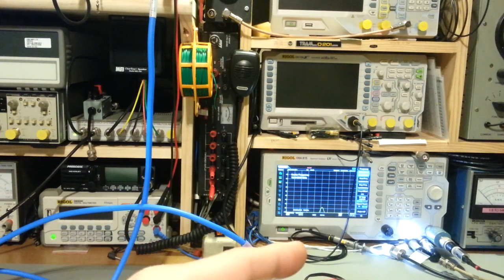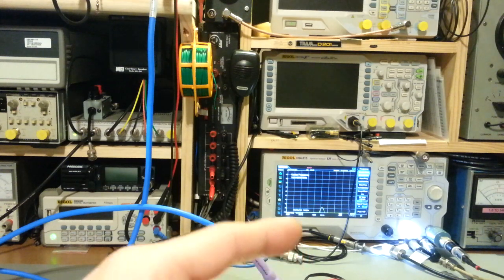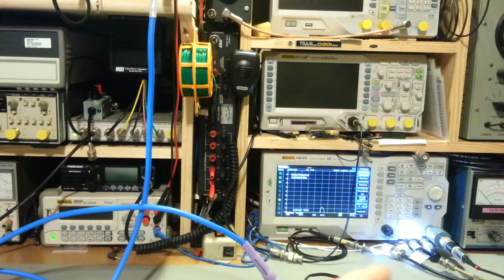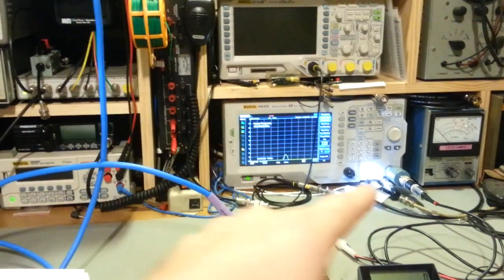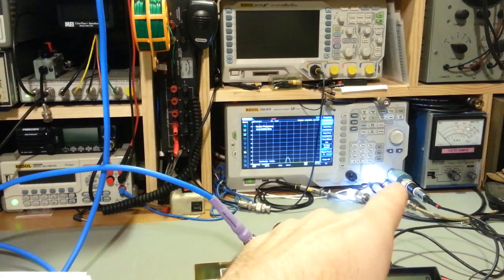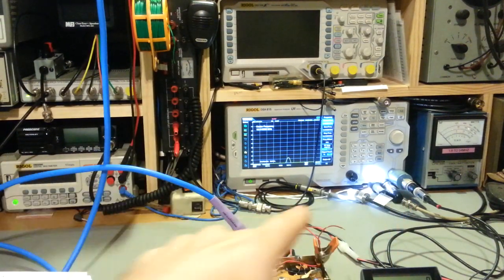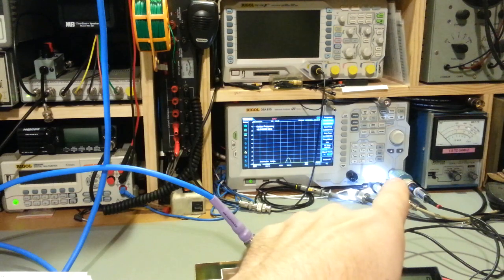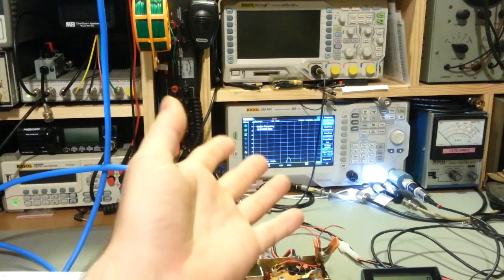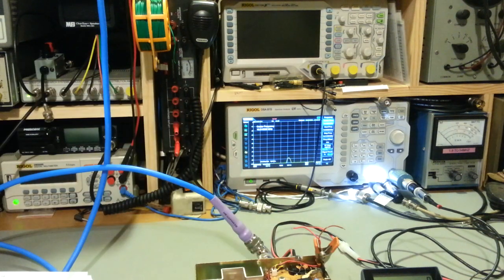They'll have a DC rating, usually printed on the front of your spectrum analyzer. It'll tell you what the maximum DC voltage is, but I always prefer to be better safe than sorry, and I put in what they call a DC block. I have a Narda brand right there, that blue thing. It's permanently attached; I just leave it there all the time. It's a DC block, and that prevents DC voltages from getting into my spectrum analyzer and causing havoc and damage.